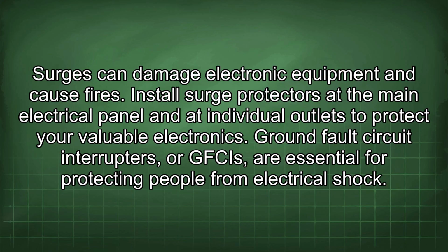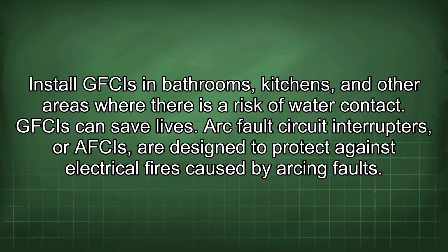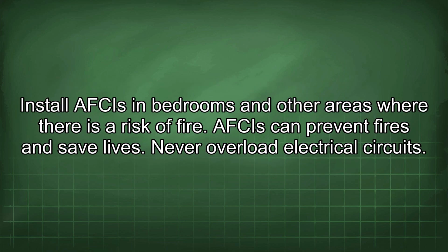Ground fault circuit interrupters, or GFCIs, are essential for protecting people from electrical shock. Install GFCIs in bathrooms, kitchens, and other areas where there is a risk of water contact. GFCIs can save lives. Arc fault circuit interrupters, or AFCIs, are designed to protect against electrical fires caused by arcing faults. Install AFCIs in bedrooms and other areas where there is a risk of fire. AFCIs can prevent fires and save lives.